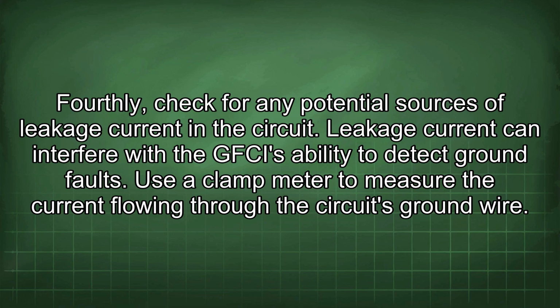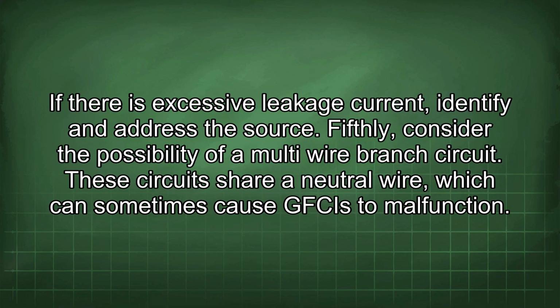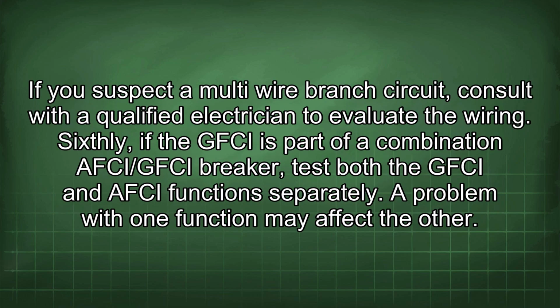Fourthly, check for any potential sources of leakage current in the circuit. Leakage current can interfere with the GFCI's ability to detect ground faults. Use a clamp meter to measure the current flowing through the circuit's ground wire. If there is excessive leakage current, identify and address the source. Fifthly, consider the possibility of a multi-wire branch circuit. These circuits share a neutral wire, which can sometimes cause GFCIs to malfunction. If you suspect a multi-wire branch circuit, consult with a qualified electrician to evaluate the wiring.